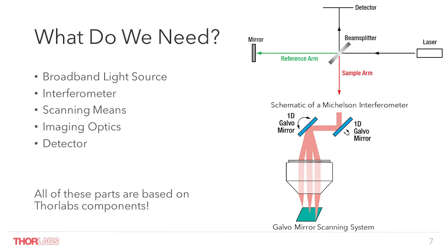The most simple configuration is the good old Michelson interferometer. In the sample arm we can raster scan our beam across the sample to get cross-sectional images, or when raster scanning in two dimensions, even a whole 3D dataset. In the bottom figure we see a scanning system that consists of two galvo mirrors and an imaging objective to focus the light beam into the sample — ideally a telecentric scan lens. Finally, the photons that are backscattered are collected again by the lens and brought to the detection unit. One of the great advantages at Thorlabs is that we have most of the components we need already in-house — OCT at Thorlabs is a great example of vertical integration.